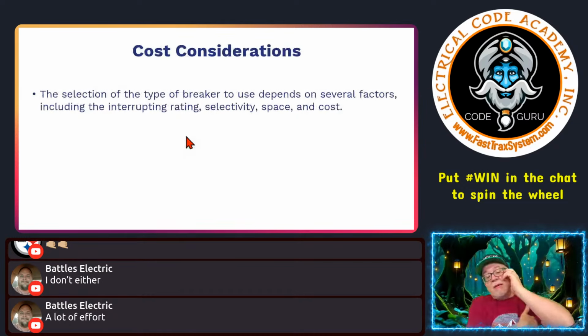So when I'm selecting breakers, fuses, and everything, it's all a matter of cost, but I don't want to sacrifice safety for cost. So selecting a type of circuit breaker depends on several factors. That includes the interrupting rating you need based on what's provided by the utility, or downstream where the code requires you to take into consideration the available fault current.